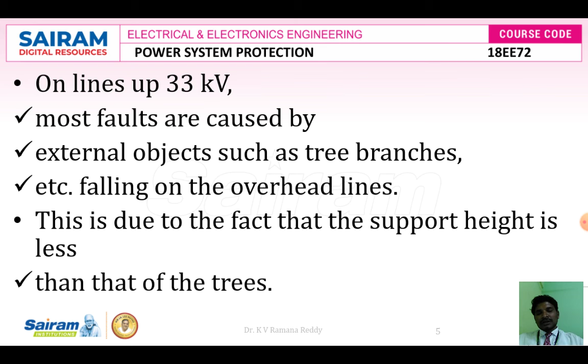And there is a tree trimming program we can do to cut the tree branches which are very near to the transmission line, and also the creepers which grow from the ground and reach our transmission line via the transmission pole. We have to remove all those things to reduce the number of faults caused on line voltage up to 33 kV. Then the external objects may not be burnt clear at the first reclosure and may require additional reclosures.